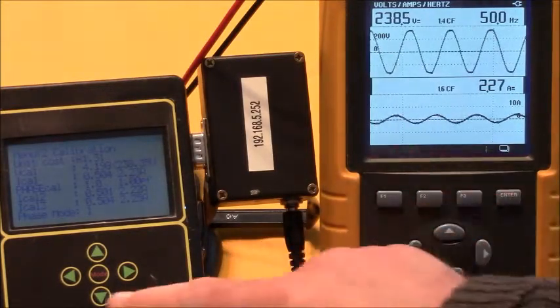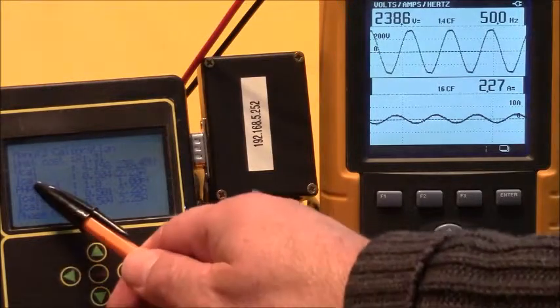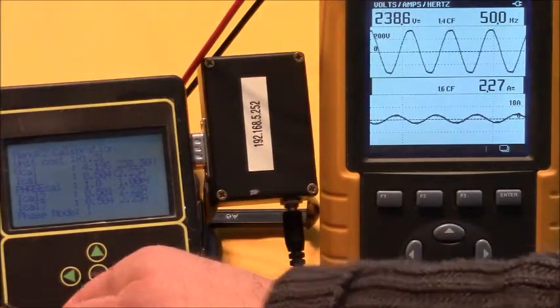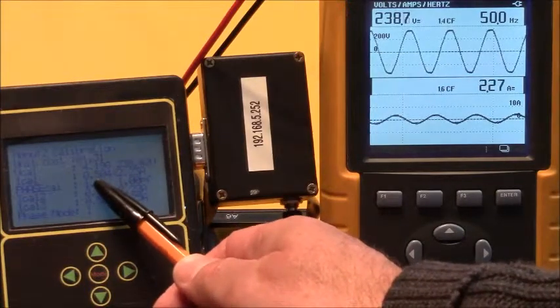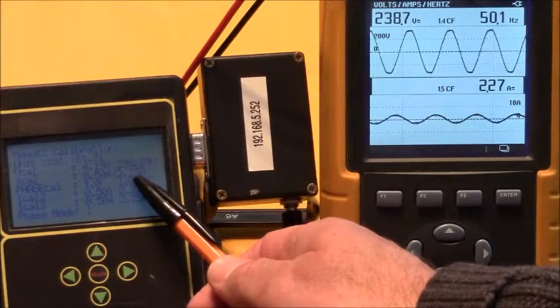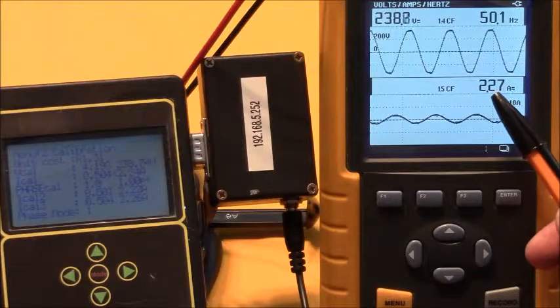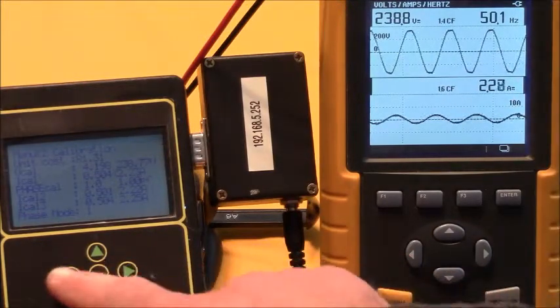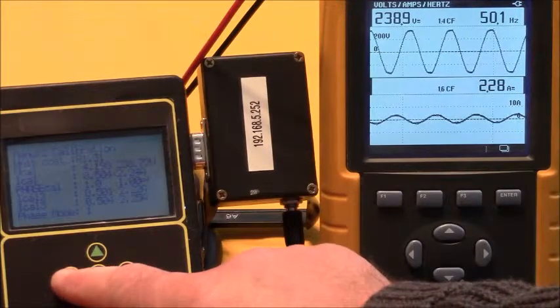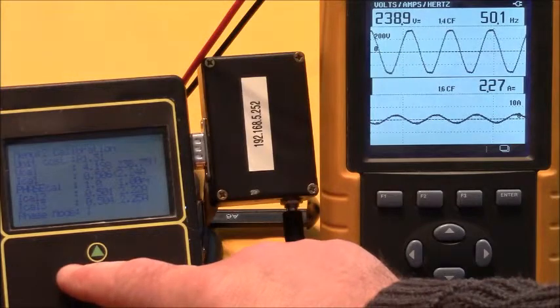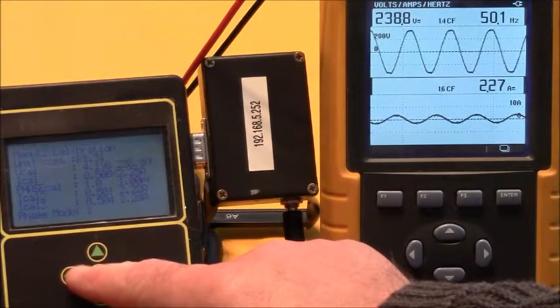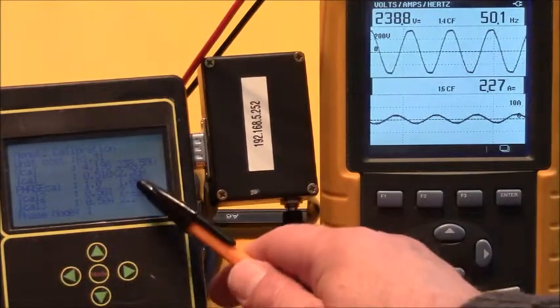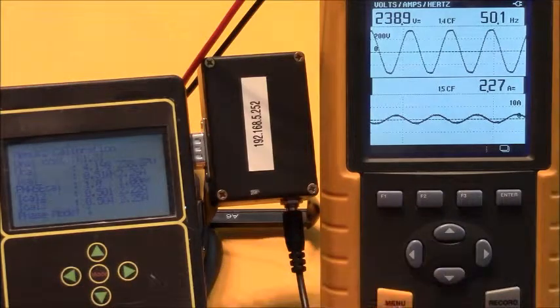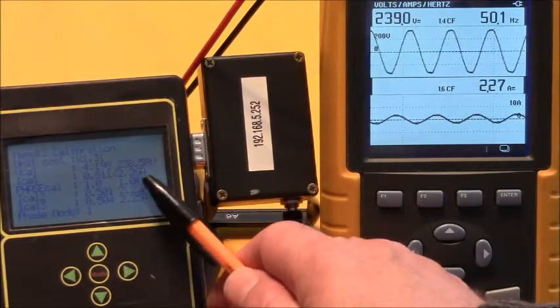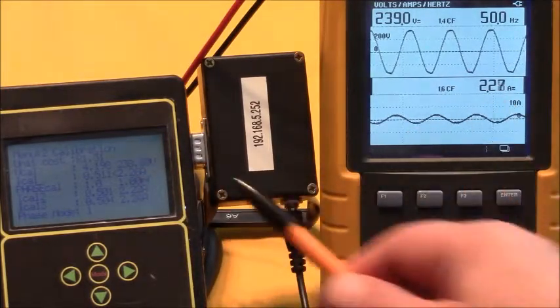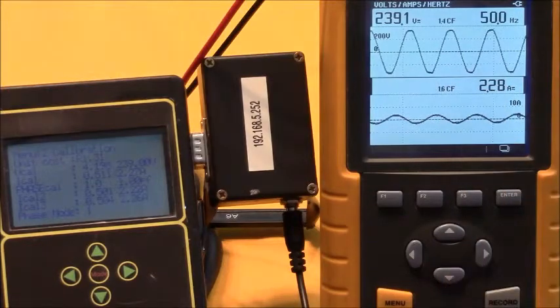Okay, when you've done that, you go down to the next one, which is current sensor number 1, the top current sensor. We've got an offset value there of 0.504, and it's showing 2.23 amps, and here it's saying 2.27. So we need to go up slightly. Now the left arrow will take that value up, and you'll find some happy point where it will actually... a tiny bit more. Okay, there we go, we're within 0.01 of an amp, which is not bad at all.